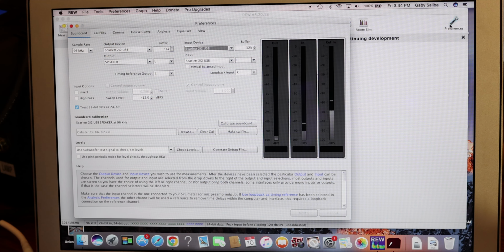Back to the software here, we're going to go on my Mac little portable computer, and we're going to exit from the preferences. Remember, we already put our sound cards here. This is on a Mac, same idea, 96 kilohertz. We got our Scarlett here. It should be at 32 and 32 here, and everything is on the left channel. So we're going to put everything on the left channel. And we've got our calibration file, it's already in here. If it's not, you could browse and find your calibration file. Then you can exit from here.